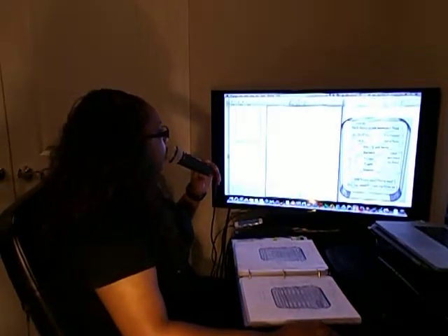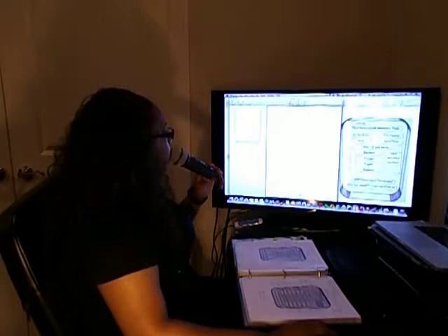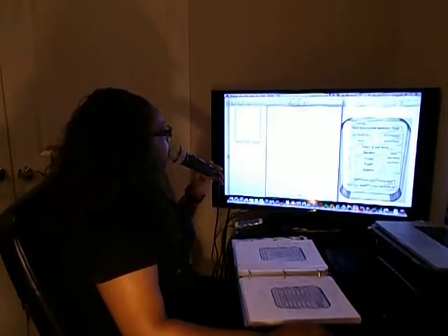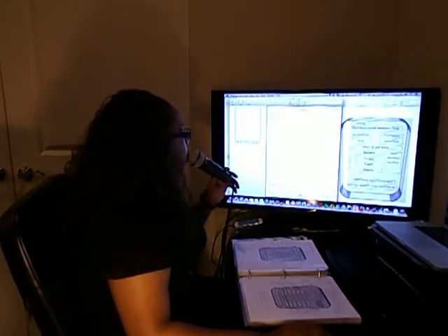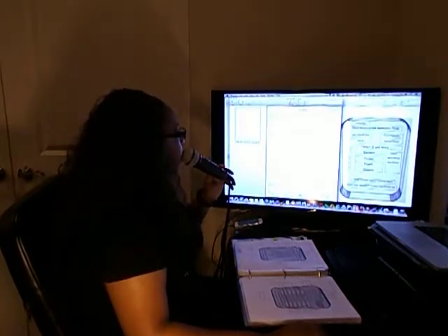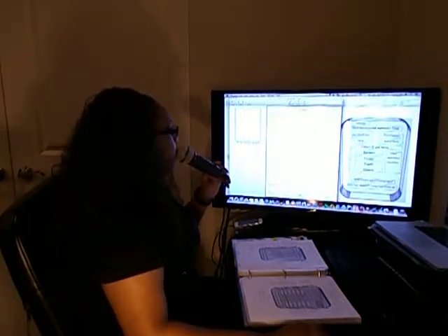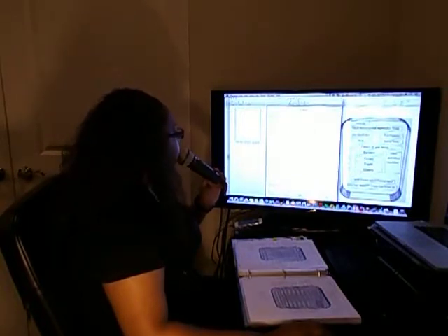Oh, also, there are alert definitions as well. We're going to go ahead and save those to go back to the alerts. It explains what each alert function is. So, for example, timestamp duplicate alerts inform the user that prior to an 8-hour minimum aeration period, the device has been or attempted to be assigned to a new patient. This practice serves as a disease transmission risk reduction mechanism. That's using the aeration period.